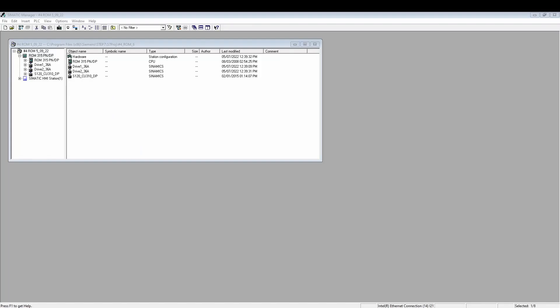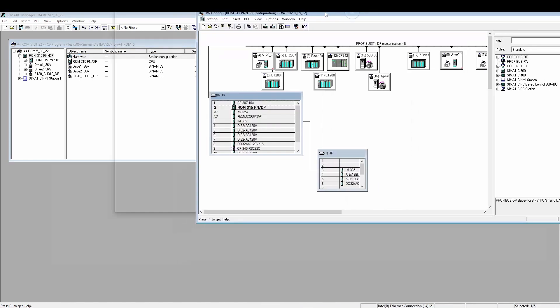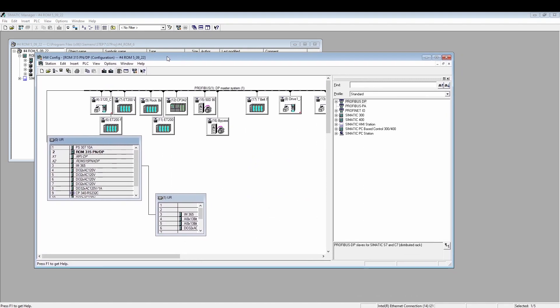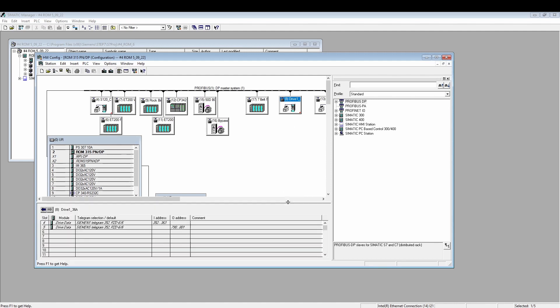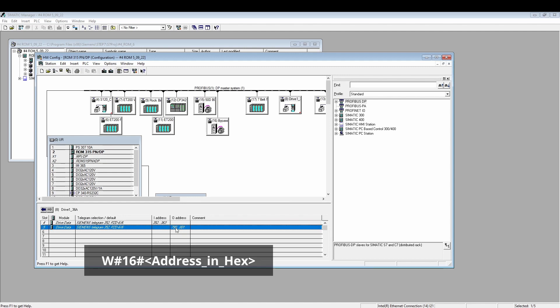Now in Simatic Manager, there's no such thing as the hardware ID. So this address is the first IO address of the device in hexadecimal format. This address can be found by selecting the device in the hardware configuration and looking in the bottom window at the first address of the input for DP read and the first address of the output for DP write and converting that number from decimal to hexadecimal. Use the following format.